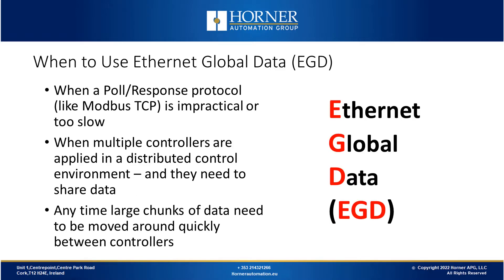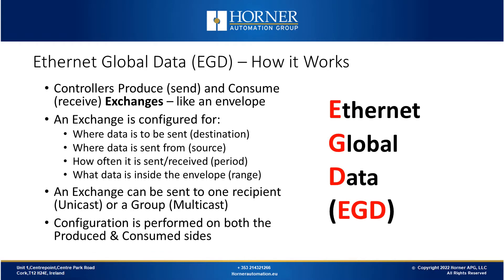So when would you use Ethernet global data? One situation is when a poll-response protocol like Modbus TCP is impractical or too slow, for example if your device needs to communicate with many server type devices. Another situation when EGD is useful is when you're using multiple controllers in a distributed control environment and they need to share data, sometimes large chunks of data quickly.